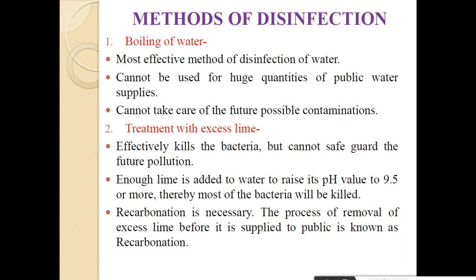Next method is treatment with excess lime. This treatment with excess lime method effectively kills the bacteria, but this cannot safeguard against future pollution of the water. In this case, enough lime is added to the water to increase its pH value to 9.5 or more, and thereby most of the bacteria will be killed. Due to the increase in pH value, recarbonation is necessary. The process of removal of excess lime before it is supplied to the public is known as recarbonation. For drinking purpose, the pH should be between 6.5 to 8, so we have to remove this excess lime and reduce the pH range to 6.5 to 8 to make the water potable. For recarbonation, we add carbon dioxide into it.